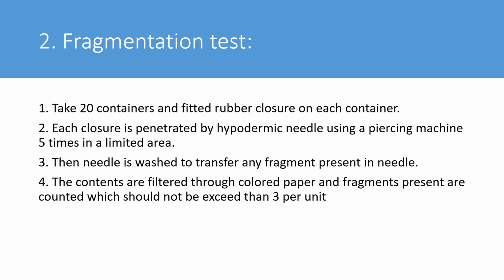Again, the test is very simple. You are trying to figure out any fragment which, while piercing the rubber closure, is actually passing into the needle. The limit allowed is that it should not exceed 3 per unit. If more than 3 fragments are found, that means it is failing the test. The rubber part is failing. If it is below the 3 level, it is passing the test.